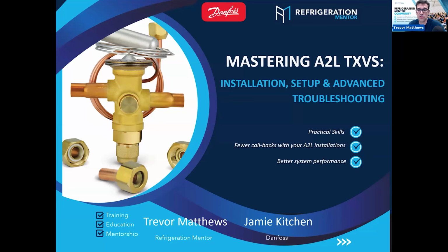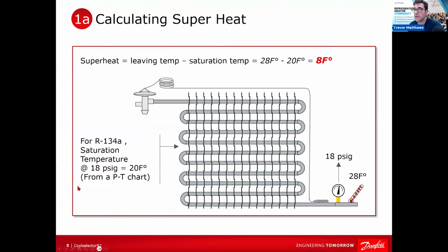Yeah. And that's so important because where we're going to dive in right now is into superheat, right? When you have a blend, it's different than when you're doing a single refrigerant. So when you had R22, it's a single refrigerant. Yeah. That really means your dew point and your bubble point are the same on your pressure temperature scale. But when we get into what Jamie was just talking about, blends where they boil off at different temperatures, that's where you get a different bubble point and dew point. Mm-hmm. And we can go into that after this because it'll be fresh in your mind.